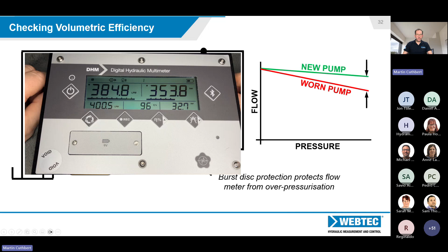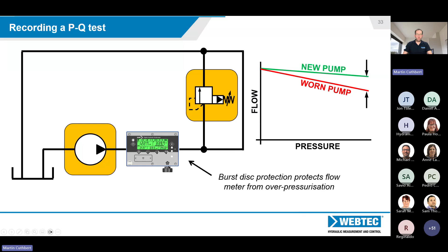So same sort of situation, the tester is installed straight after the pump and before the relief valve, but we might want to actually carry out a full PQ test. What we mean by that is carrying out a test at full flow under no load, and then progressively loading it and recording the performance of the pump over those different pressures. So similar to the volumetric efficiency test, but we're actually carrying out some recordings as we go along. Let's just see how that would work. So if we just go to, let's say, about here.